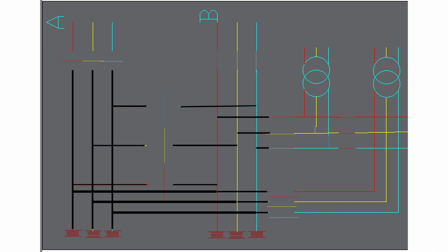You open the first isolator on the transformer side, but before that, you close the bus coupling isolator of the two transformers. Then both the transformers will be charged for parallel running. And if parallel running is not required, then it's very simple. One transformer will always be in circuit. In railway generally we use one transformer, but during overload we can make it parallel.